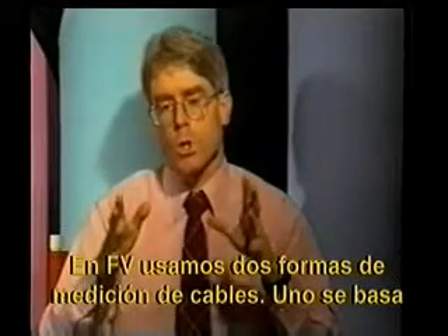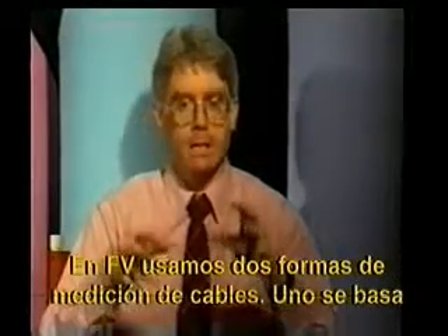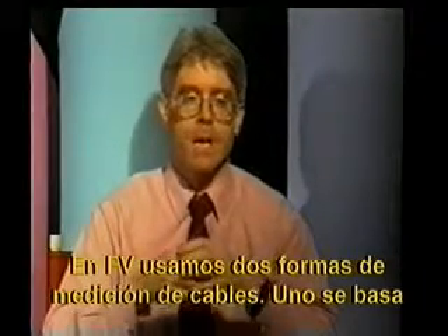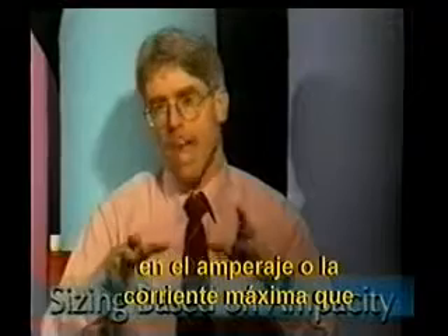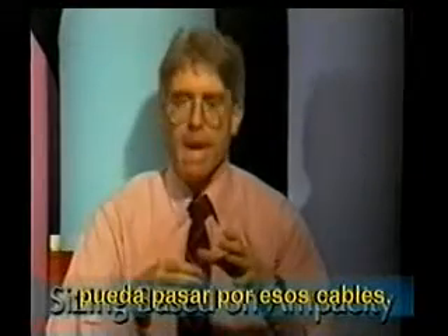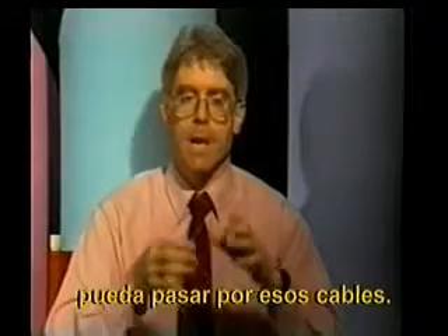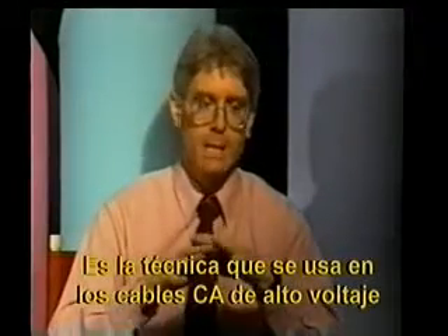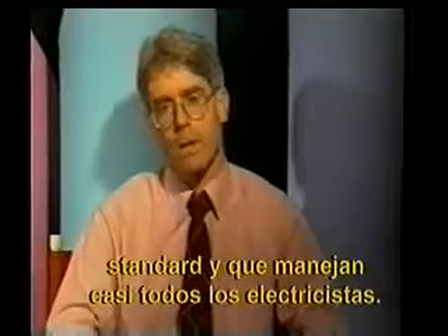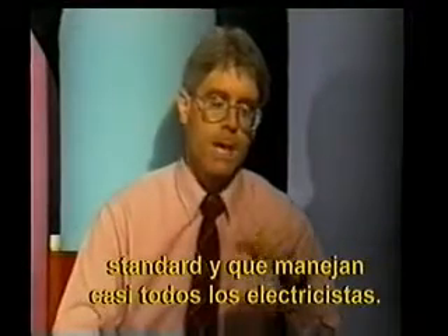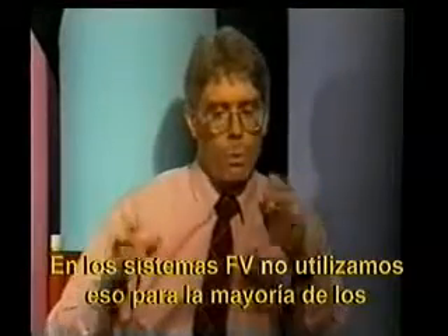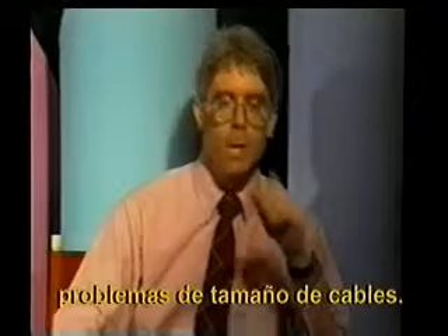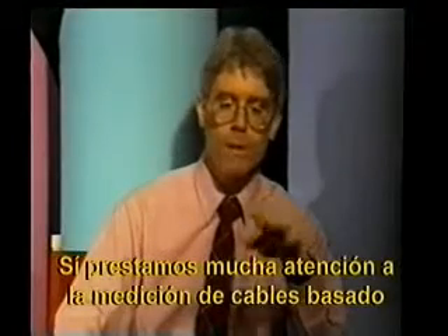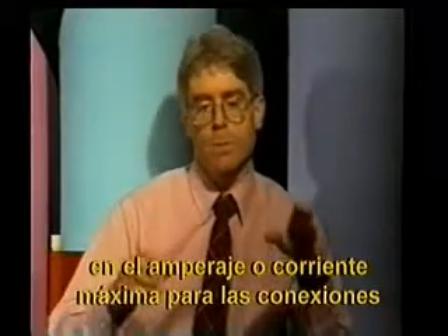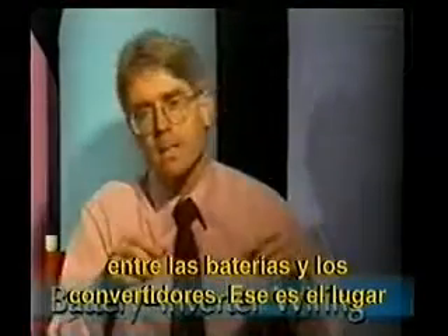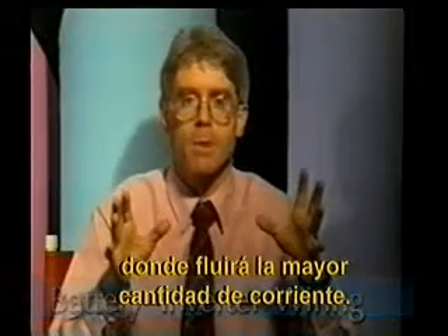There's really two approaches to wire sizing that we use in photovoltaic system design. One is wire sizing based on ampacity, basing the wire size on the maximum current that might be flowing through it. This is typically the technique that's used in standard high voltage AC wiring as well. That's what most electricians are going to be used to. In photovoltaic systems, we don't use that for the majority of our wire sizing problems. We do pay a lot of attention to wire sizing based on ampacity for the connections between our batteries and our inverters. That's the location where the largest amount of current is going to be flowing.